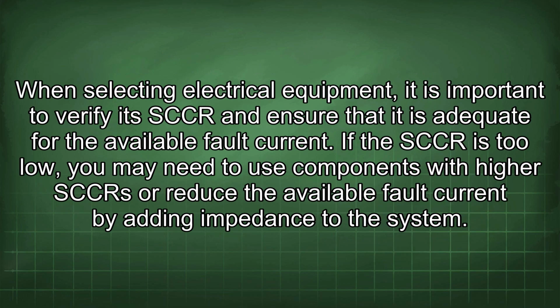When selecting electrical equipment, it is important to verify its SCCR and ensure that it is adequate for the available fault current. If the SCCR is too low, you may need to use components with higher SCCRs or reduce the available fault current by adding impedance to the system.